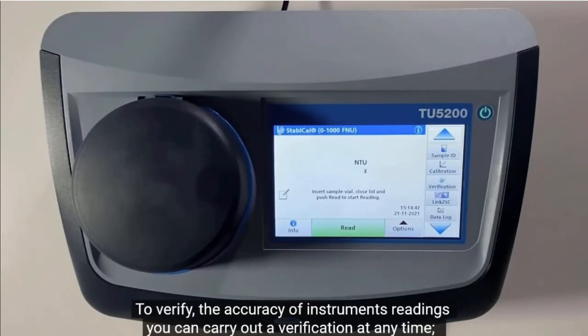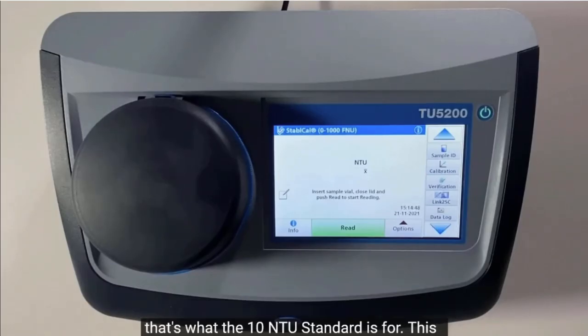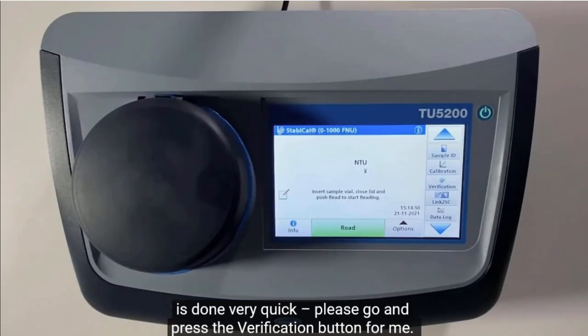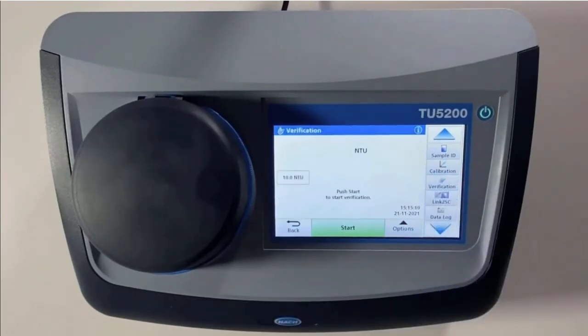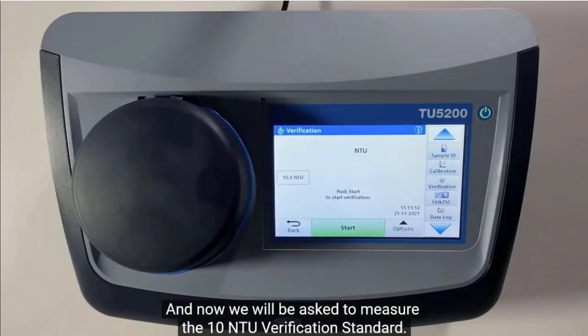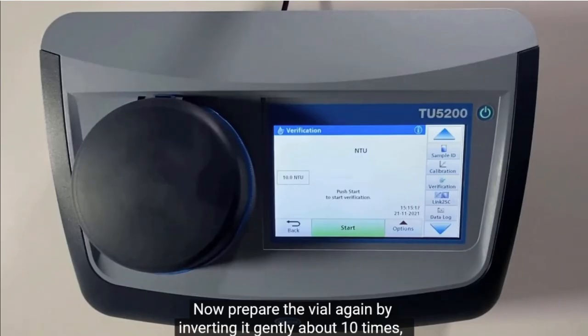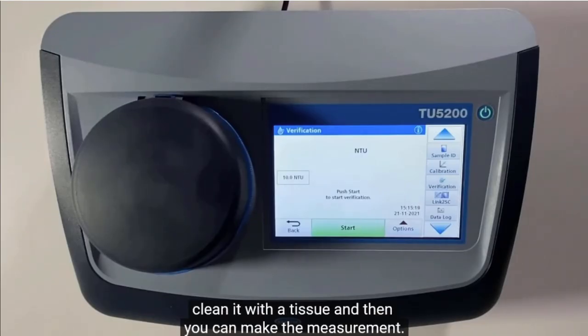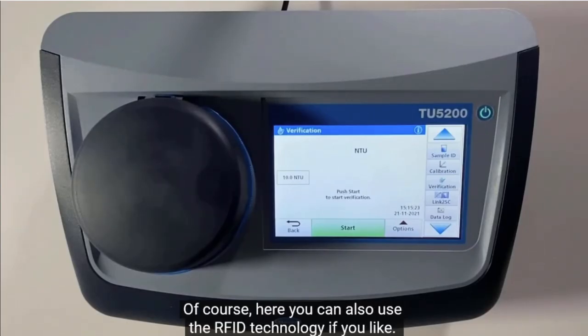Mrs. Kessler, to verify the accuracy of the instrument readings, you can carry out a verification at any time. That's what the 10 NTU standard is for. This is done very quickly. Please go and press the verification button for me. Thank you very much. And now we will be asked to measure the 10 NTU verification standard. Now prepare the vial again by inverting it gently about 10 times, clean it with a tissue, and then you can make the measurement. Of course, here you can also use the RFID technology if you like.